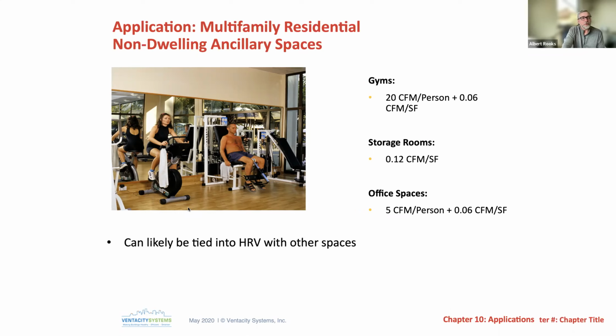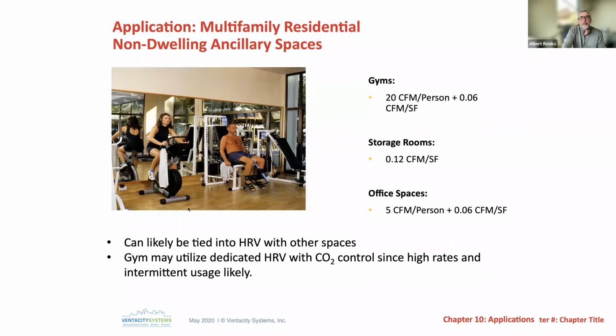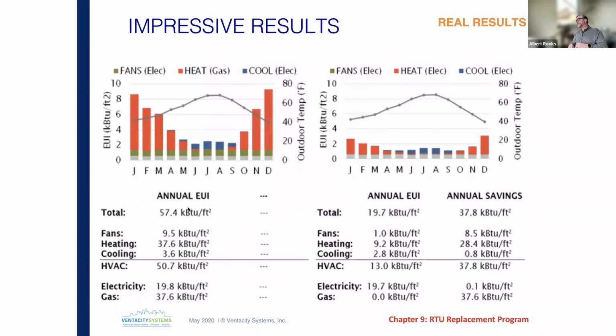So we just got to look at the whole building and create the right ventilation design for it, divide out the small occupied suites from the corridors, public spaces, laundry rooms, things like that. And that would be a pretty good pathway forward to retrofit these buildings. And it's really all about getting in there and managing the duct requirements. That's really kind of the holdup in doing these things. So I'm pretty happy that we see ways around this.